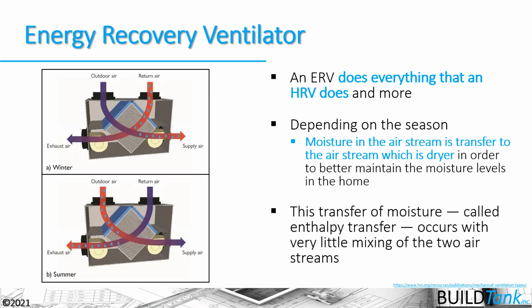And by doing that, we're starting to see that the old rule of thumb is no longer really the case, which was that heat recovery ventilators were for cold northern climates and energy recovery ventilators were only for warm, humid climates. They do a good job of ensuring that moisture from the outside isn't coming into that house excessively in hot, humid climates. But we're starting to see more and more energy recovery ventilators being installed in colder climates as well to help control the indoor relative humidity inside that house. On the flip side, we shouldn't be seeing heat recovery ventilators installed in warm, humid climates because it's just going to pump that moisture outside into the house, and we don't want that.